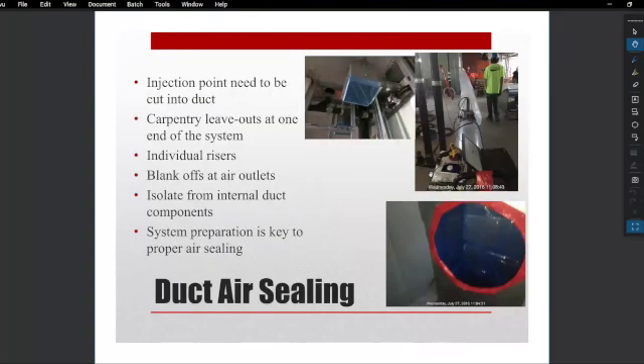The entire system has to be complete before air sealing can begin, and this usually coincides with sheetrock activities. So we have to coordinate with the carpenter for leave-outs, because, as you can see in the picture below, you need some space to do the run-out for the discharge of the AeroSeal unit, and you need to have a cutout in the riser to inject the air seal.